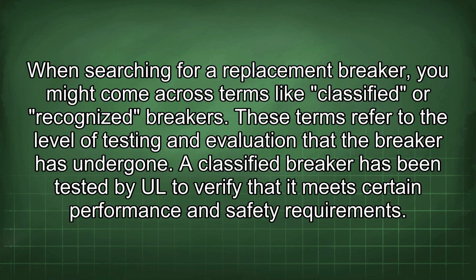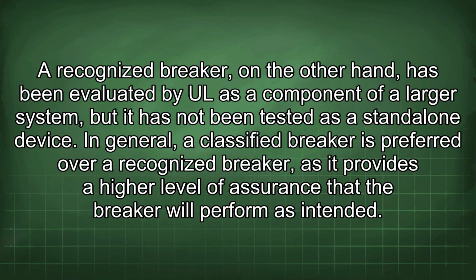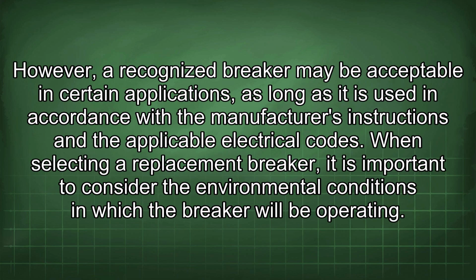These terms refer to the level of testing and evaluation that the breaker has undergone. A classified breaker has been tested by UL to verify that it meets certain performance and safety requirements. A recognized breaker, on the other hand, has been evaluated by UL as a component of a larger system, but it has not been tested as a standalone device. In general, a classified breaker is preferred over a recognized breaker, as it provides a higher level of assurance that the breaker will perform as intended. However, a recognized breaker may be acceptable in certain applications as long as it is used in accordance with the manufacturer's instructions and the applicable electrical codes.